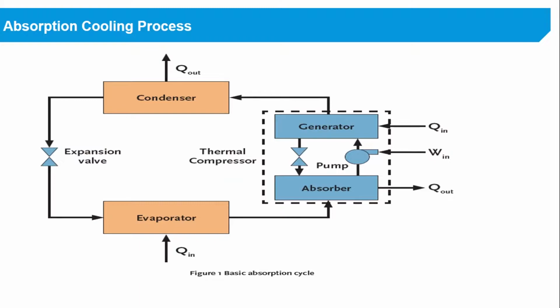The solution starts to boil due to the heat, turning water into vapor, which flows to the condenser. The condenser liquefies the water vapor, rejecting heat in the process, which is collected by the heat sink. The new liquid condensate is then directed toward the evaporator through an expansion valve. Finally, evaporation of the refrigerant at low pressure causes the evaporator to absorb heat from the cooled space, creating the cooling effect. At the end, vaporized refrigerant returns to the absorber and the cycle repeats.